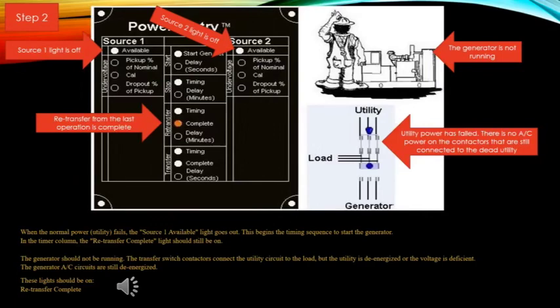The re-transfer from the last operation is still indicating complete. Source two light is not on and will not come on until the generator starts. The generator is not running. The utility power has failed, and there is no AC power on the contactors that are still connected to the dead utility.